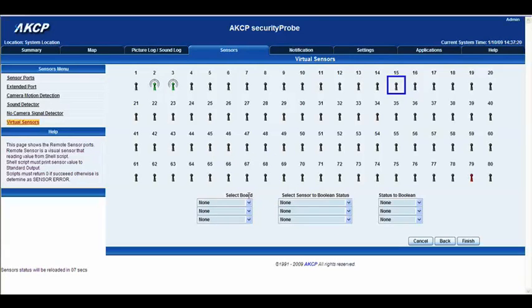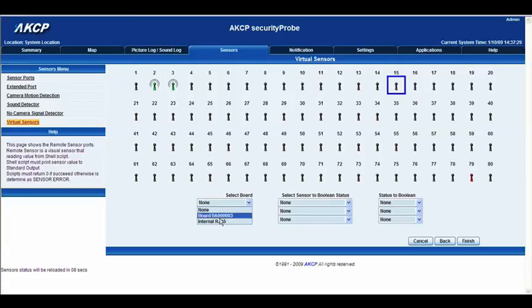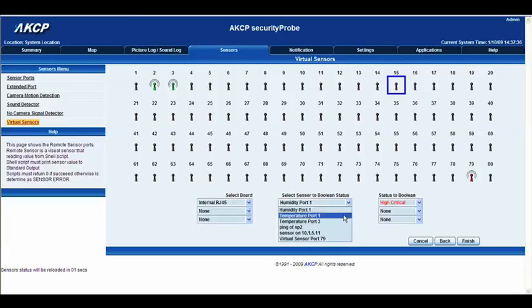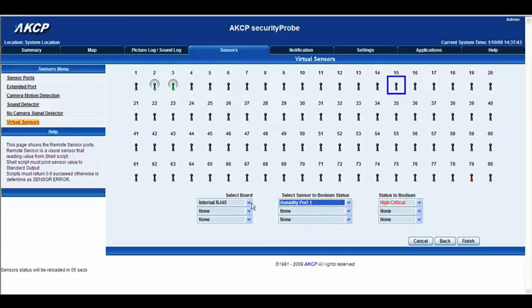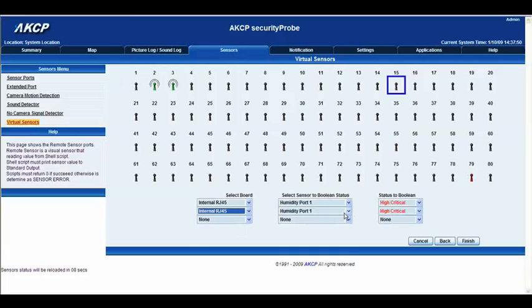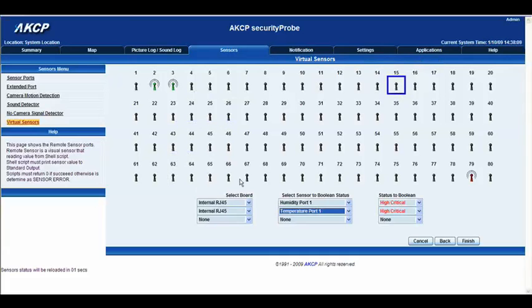First of all we've got the Select Board. You have three options here, or maybe even more depending on how many expansion ports you've got plugged into your SecurityProbe 5e. We're going to select the internal RJ45 board. On that board, let's select Humidity port 1 and set the status to Boolean High Critical. For the next one, let's take the internal board again and select Temperature on port 1, also set to High Critical. What will happen is when these two sensors both hit High Critical, this Virtual Sensor will also display a High Critical status.